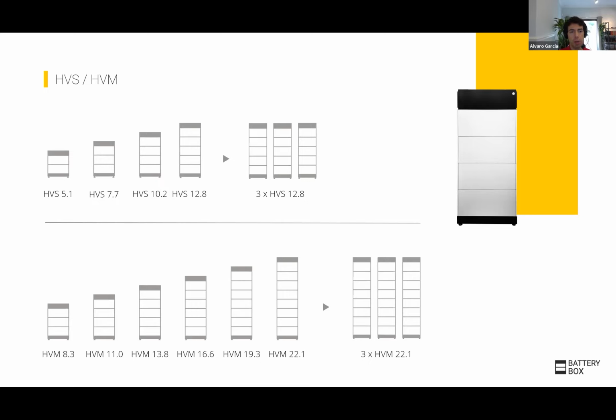The HVS batteries are each 100 volts per module, so you put two together to make 200 volts, and as you add more modules the voltage of the system increases. These are direct high voltage systems, done to maximize the efficiency of the battery. But this means the voltage of the battery system changes depending on the number of batteries, so take this into consideration when pairing with an inverter.